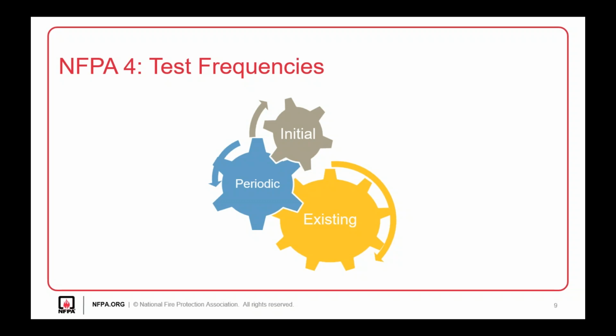Going back to highlight initial testing frequency: integrated system testing occurs during the construction phase and may coincide with the acceptance testing of individual systems. This initial test is a comprehensive test based on the test plan prepared by the integrated testing agent and approved by the authority having jurisdiction. There was really no controversy on this subject from the technical committee over mandating an integrated system test for all new buildings, after the acceptance testing of each individual system.